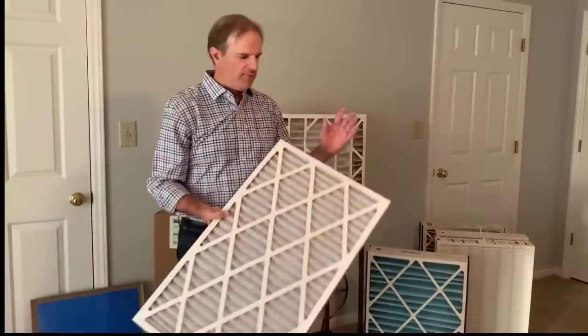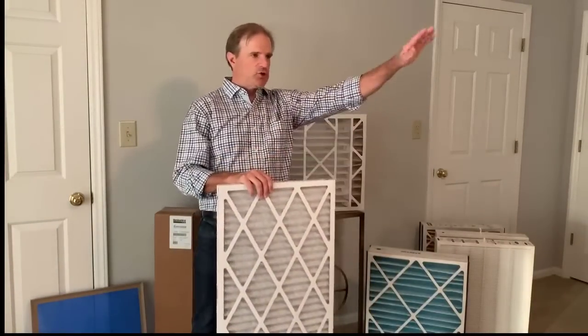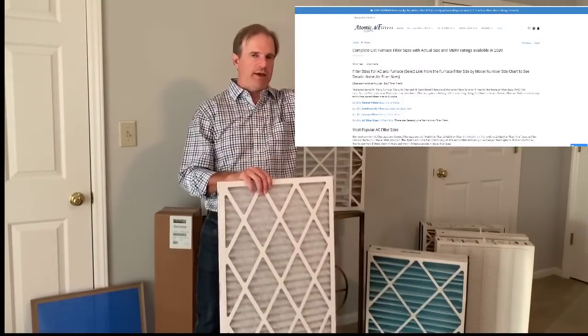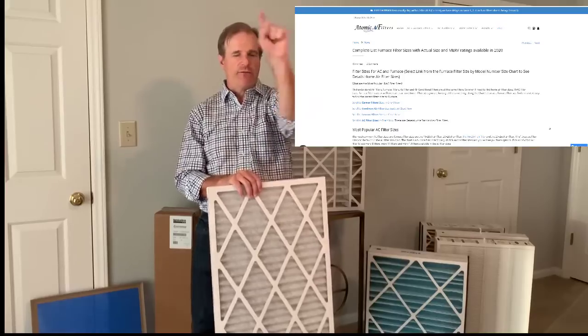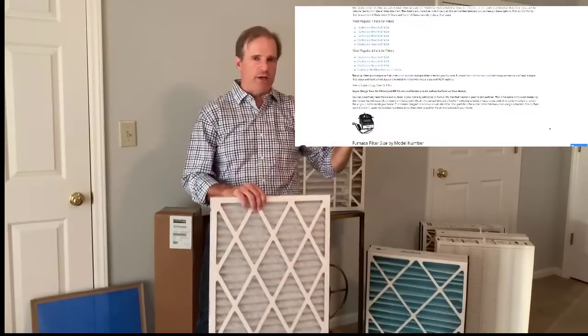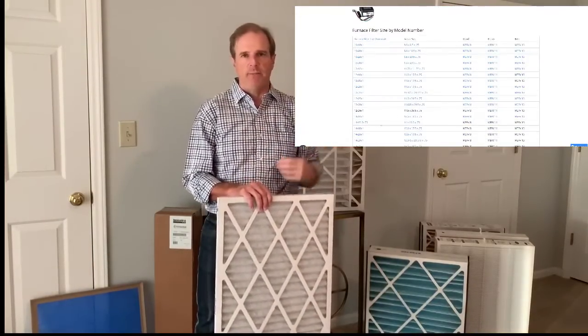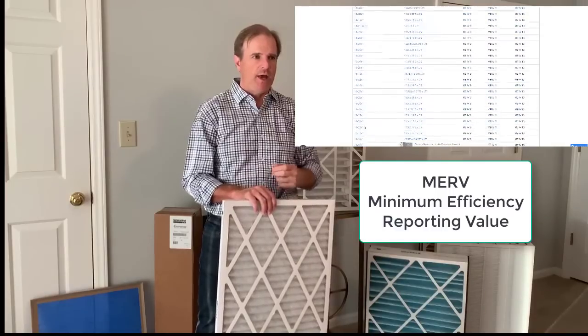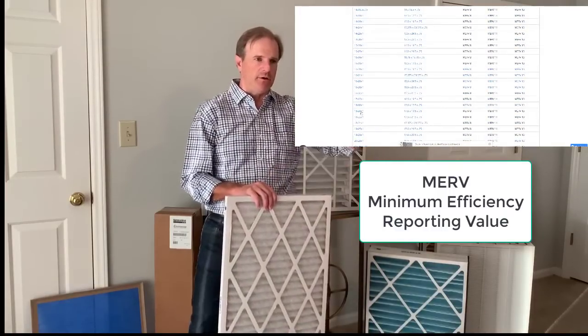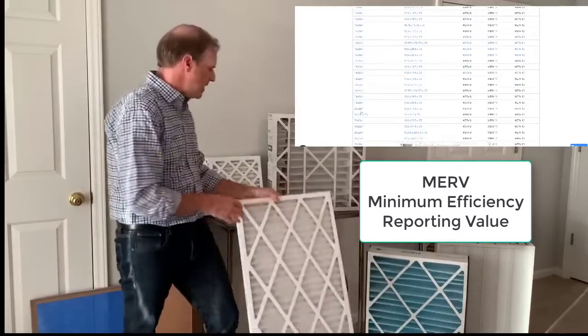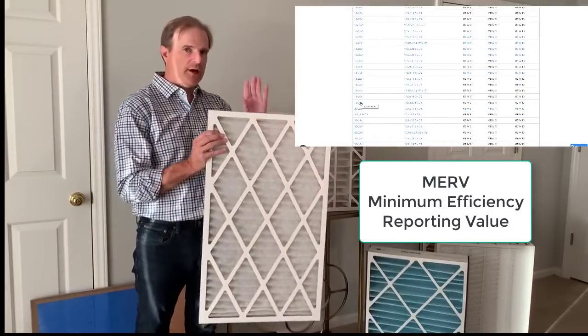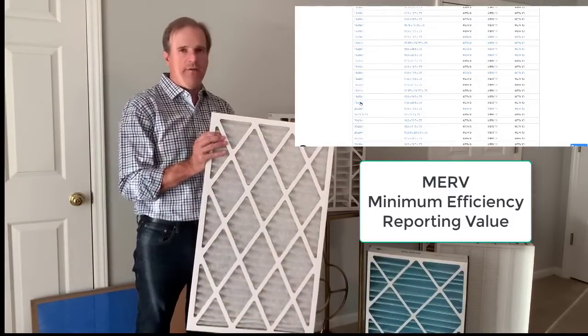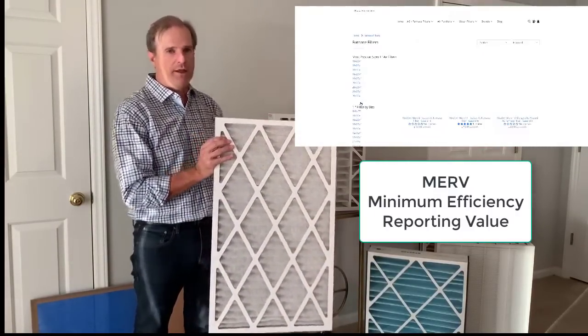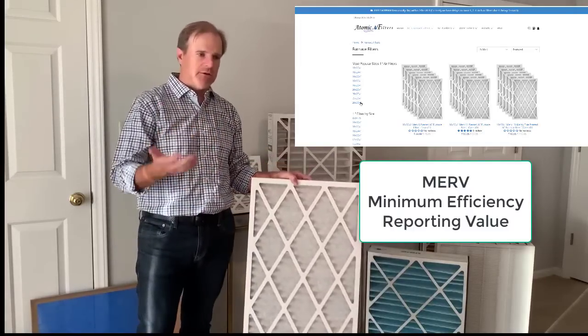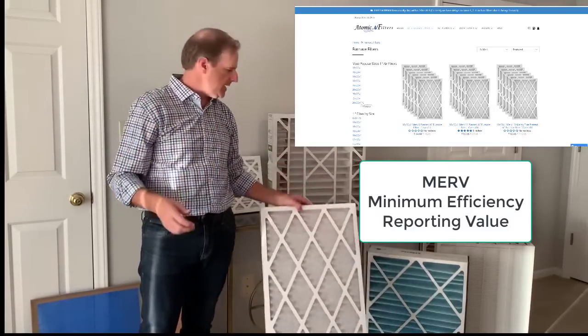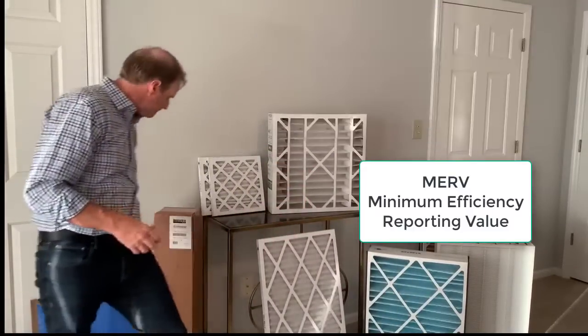And you want to make sure that when you're looking at the chart, it's going to have the nominal size and then the actual size and then 3 levels of filtration, which is called MERV. It's the minimum efficiency reporting value, and that's the efficiency of the filter. The higher the number, the more efficient. So this is a MERV 8 filter, and this is the first level that starts to protect air quality. And the higher you go, if you have allergies, MERV 11 or 13 might be a better choice.